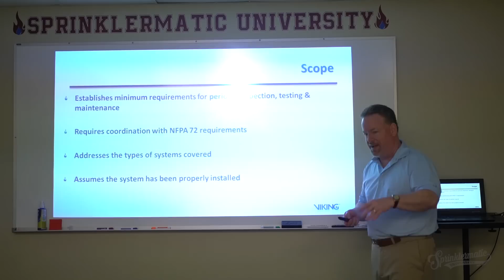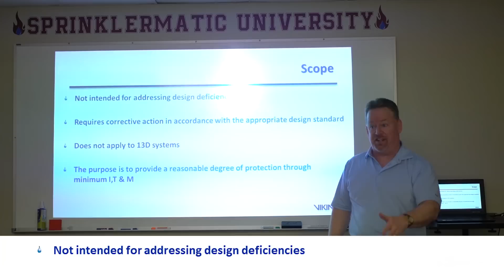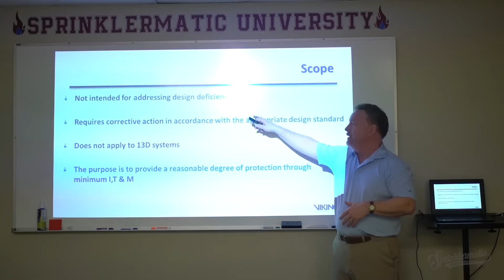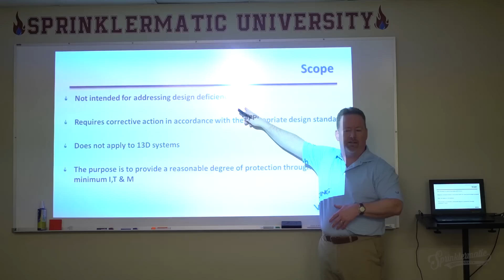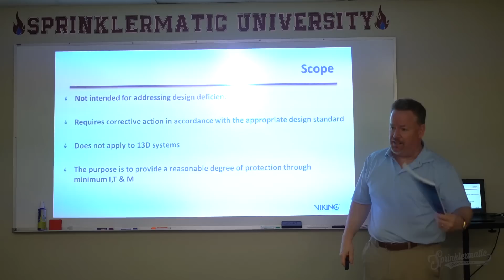If the inspection technician walks in, and this room used to be a classroom the last time he was in here, and now it's a storage room, this is not something that he can cite in NFPA 25, design deficiencies. Unsprinklered areas, things like that. There's not any place where they can cite it. That's a design deficiency. So while the inspection technician can't get there in NFPA 25, the AHJ, the other part of that triangle, absolutely can get there and cite them for design deficiencies or for unsprinklered areas, things like that.